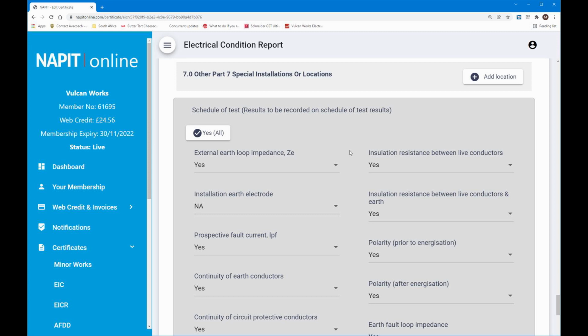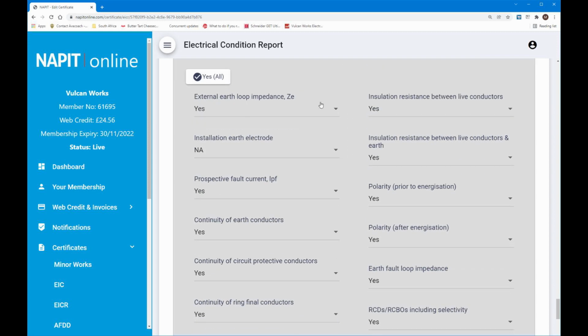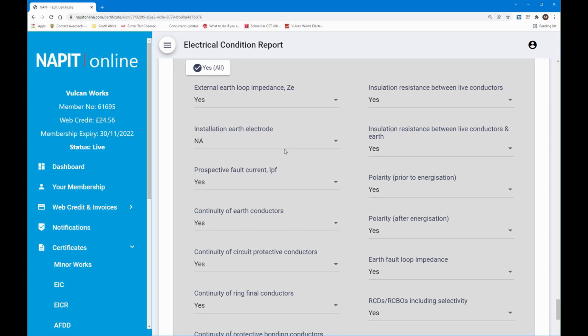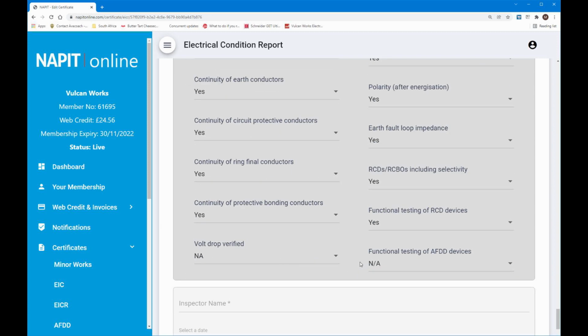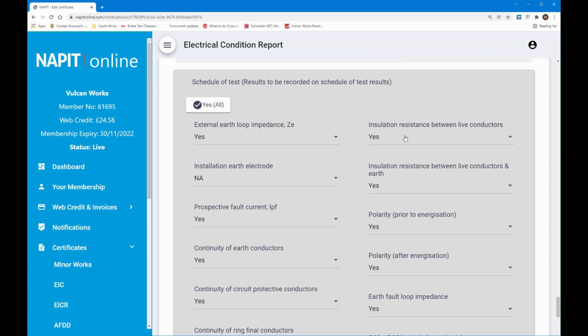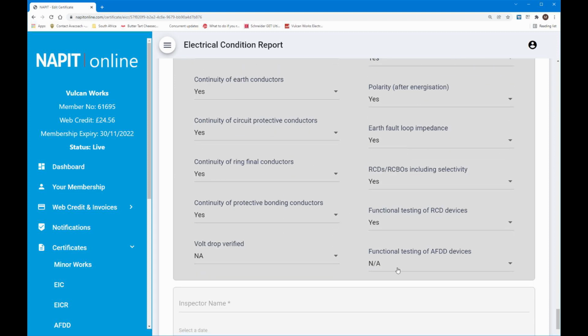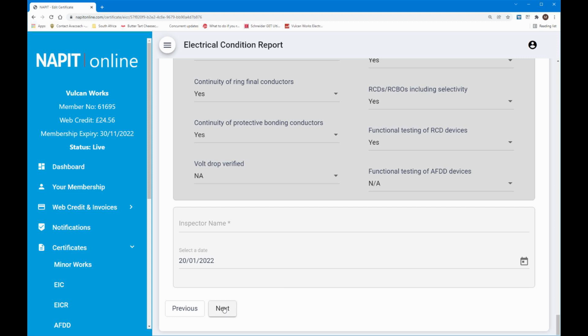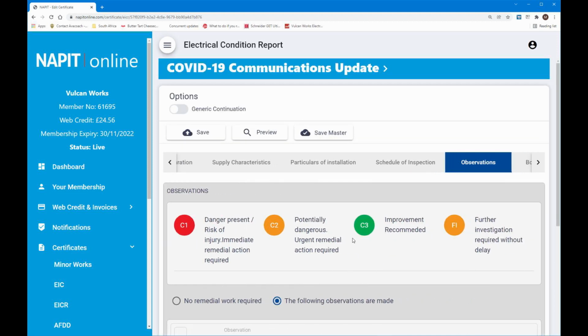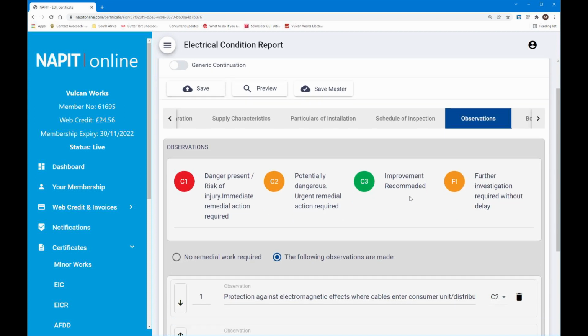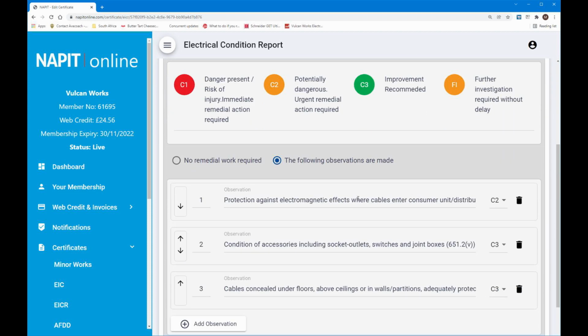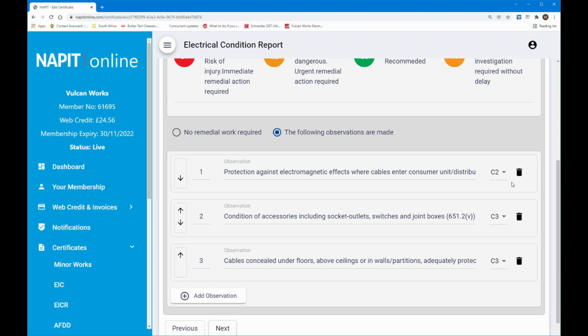Okay, so we go on to this bit. So schedule of tests, what's in here. So that was done, there's no earth electrodes, no volt drop was necessary on this. That was all done, and there was no AFDDs, thank God. So we'll go on to the next bit. So this is just the observations that have come up. So in brief, that's a C2, so it needs to be dealt with. These two are C3s. They can be dealt with, they don't have to be, that's up to the client.